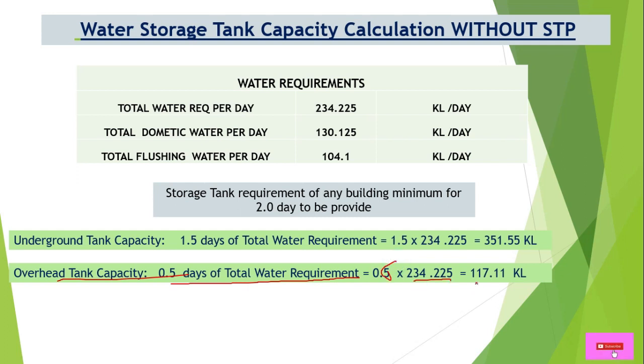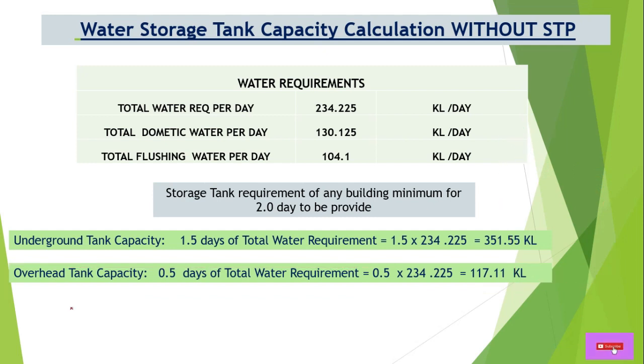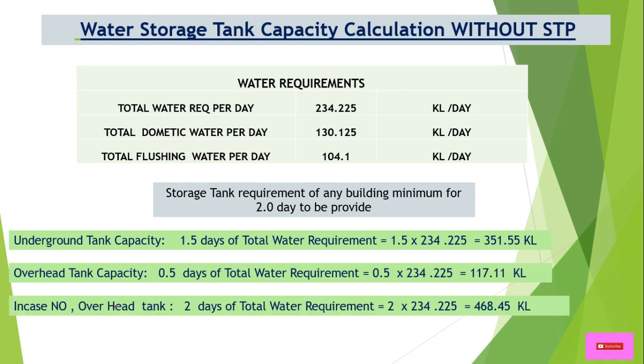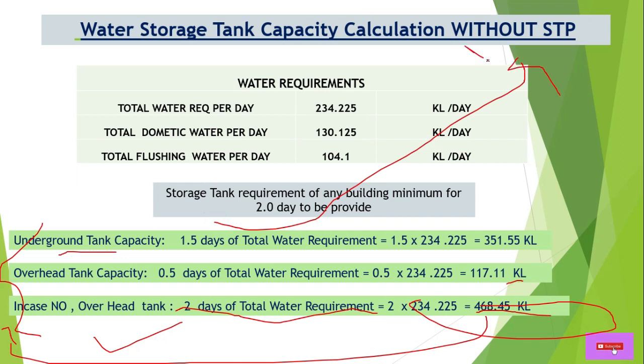If there is no overhead tank — for example, if the building structure cannot accommodate one — then we size the underground tank for 2 days of total water requirement: 2 × 234.225 = 468 KL. This concludes the without-STP calculation.